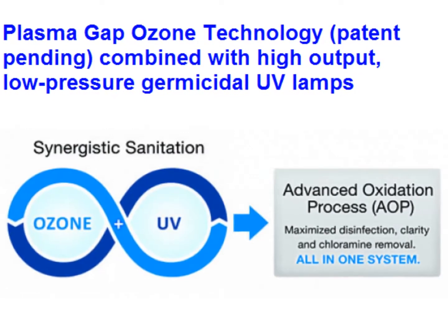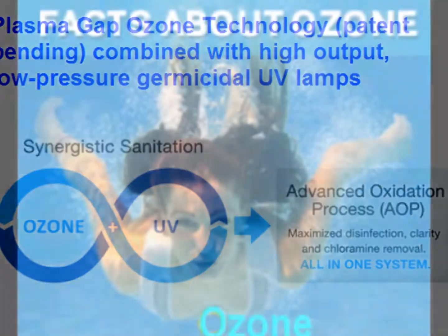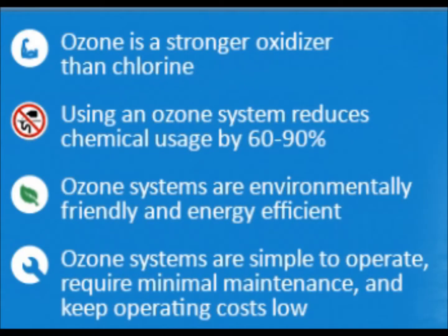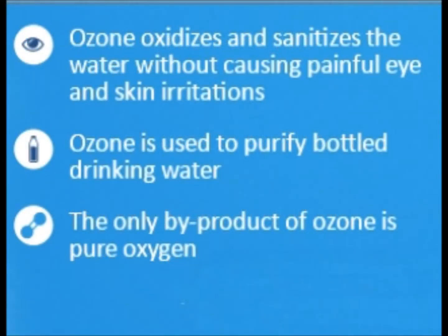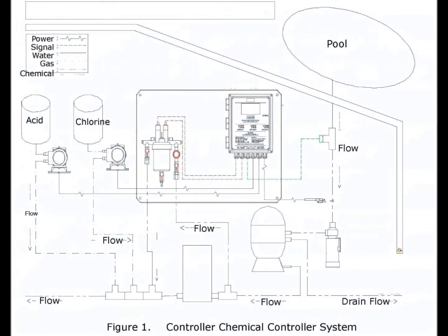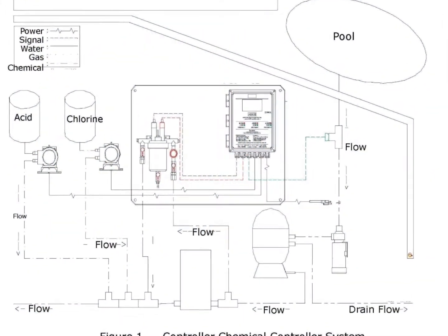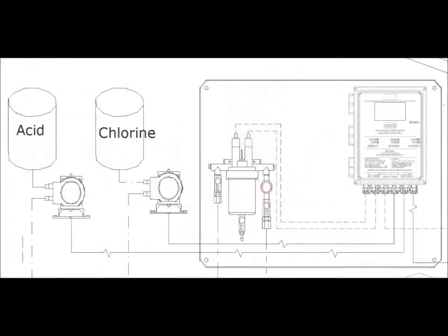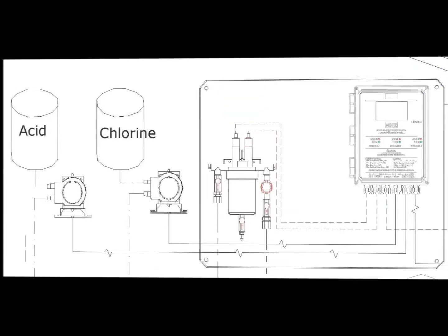If you would like to mitigate the use of chlorine, our recommendations are to use 3 widely known and most often employed technologies in combination with one another. By utilizing these 3 types of sanitizing, you will be providing the healthiest and friendliest water environment for swimming. This starts with incorporating an ORP pH doser system, which will be able to provide the minimum levels of measurable and verifiable sanitizing that is recognized by health officials.